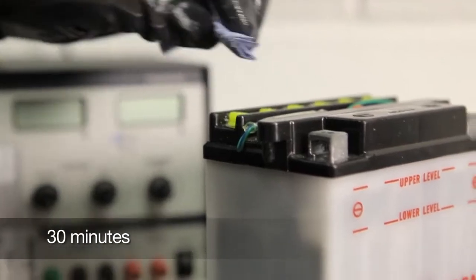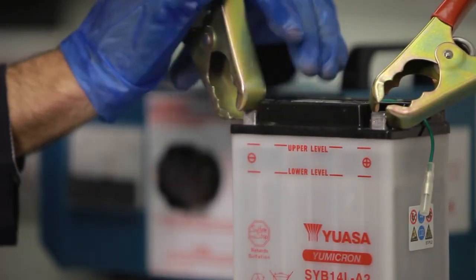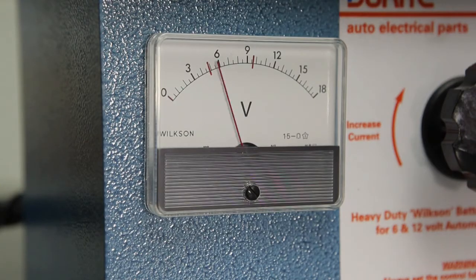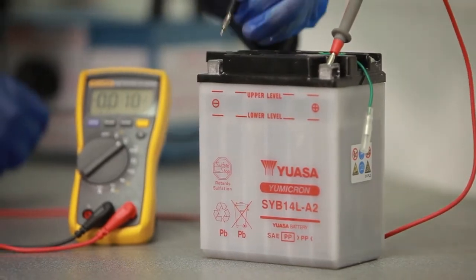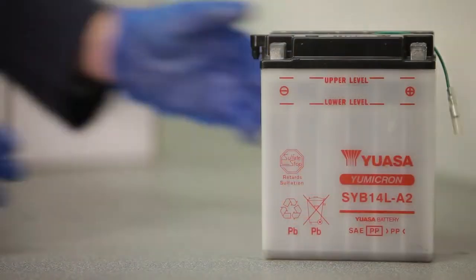Allow the battery to stand for at least 30 minutes, then load test it at three times its ampere-hour rating for 15 seconds, or use an automatic battery tester to determine the battery's condition, and then check the voltage. This should be a minimum of 12.4 on a 12-volt battery. The battery is then ready to be fitted.